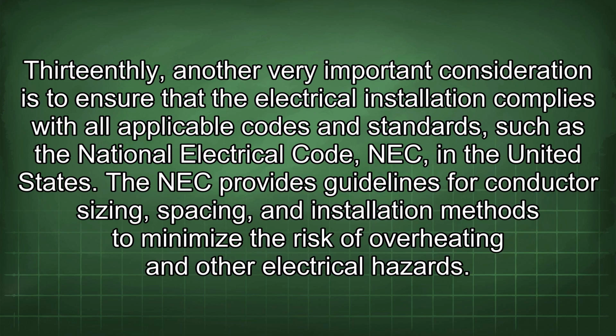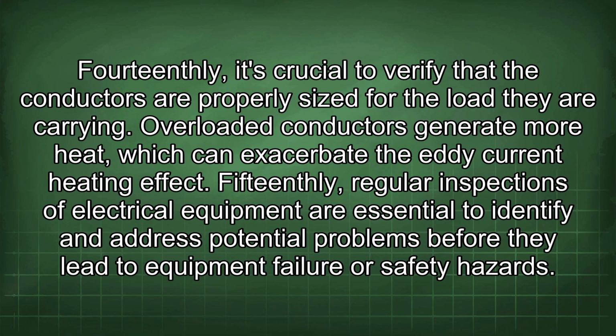Thirteenthly, another very important consideration is to ensure that the electrical installation complies with all applicable codes and standards, such as the National Electrical Code, NEC, in the United States. The NEC provides guidelines for conductor sizing, spacing, and installation methods to minimize the risk of overheating and other electrical hazards. Fourteenthly, it's crucial to verify that the conductors are properly sized for the load they are carrying. Overloaded conductors generate more heat, which can exacerbate the eddy current heating effect.